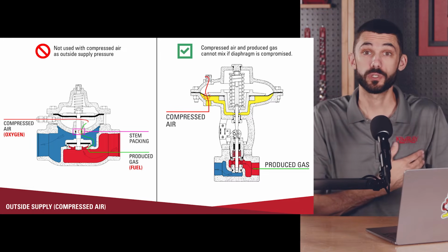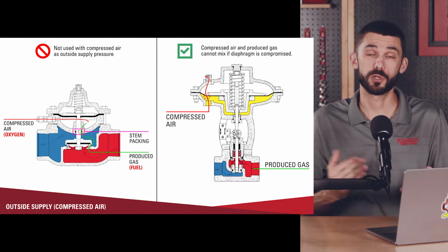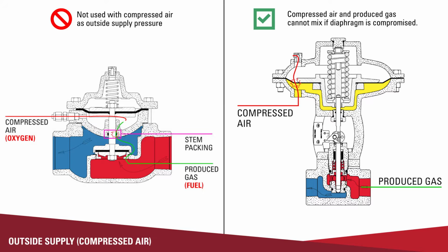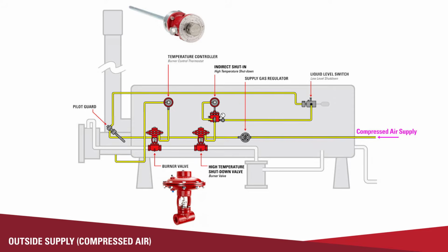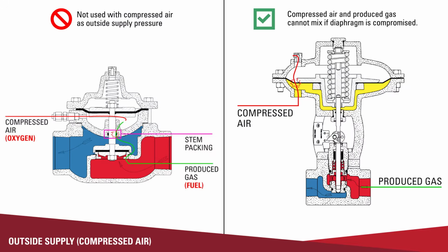So if the temperature controller is operating a high pressure control valve, so any valve found in section CV of our catalog, the actuator of that valve is completely separated from the process flow. In those scenarios, you can use compressed air for the pneumatic signal and supply for the temperature controller. You want to be careful that you're not using compressed air with any controller, any low pressure burner valve that's found in section B of our catalog.